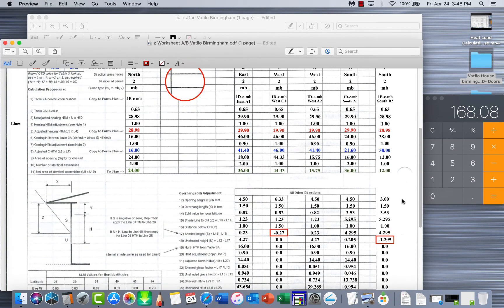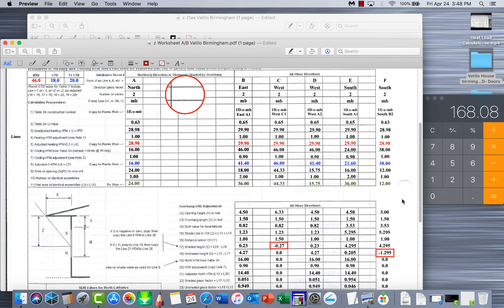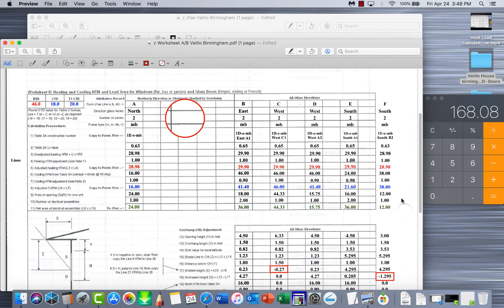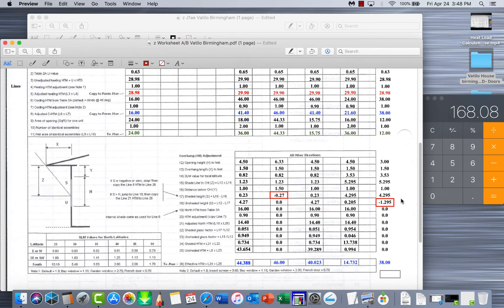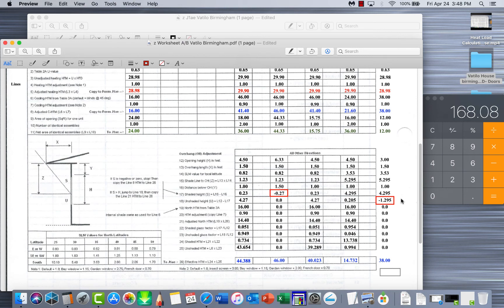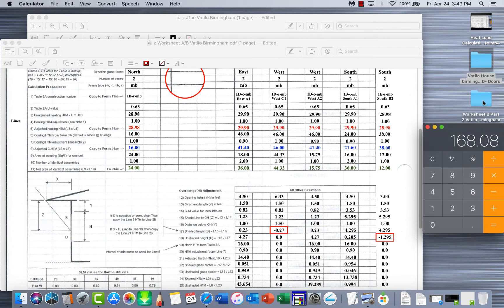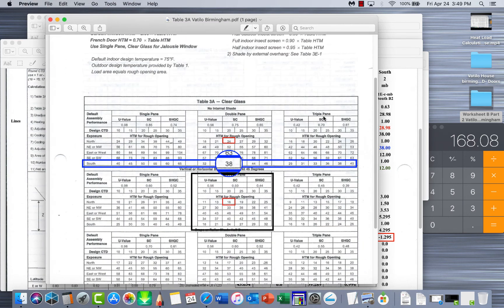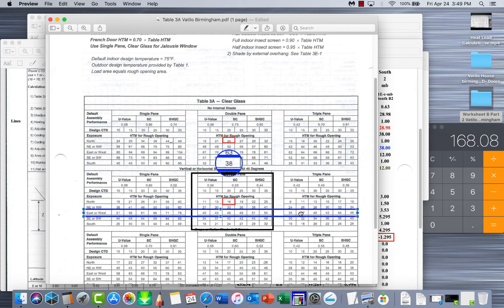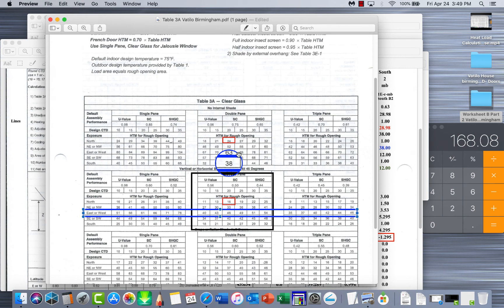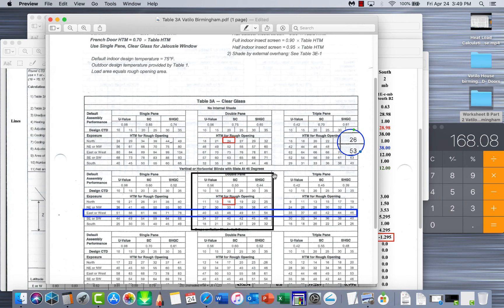But these are your final calculations for the Valtilo house that is in Birmingham, Alabama. So if you're doing this work along, remember to round to the thousandths place and make sure that you're getting kind of the same number. If you don't get the same number, look and see on your charts if you're on the correct charts. That is the only warning I'll give you about this window right here. The only difference between this window right here, which was a daylight window, it has no shade or nothing like that. Let me bring that up and show that to you real quick before we leave this. If you go to your windows, we've been working down here in these windows. In other words, the windows that are vertical horizontal blinds at 45 degrees, that's a default. We're just using that as default because we don't know what they're actually going to put in there, and this is kind of middle of the road.